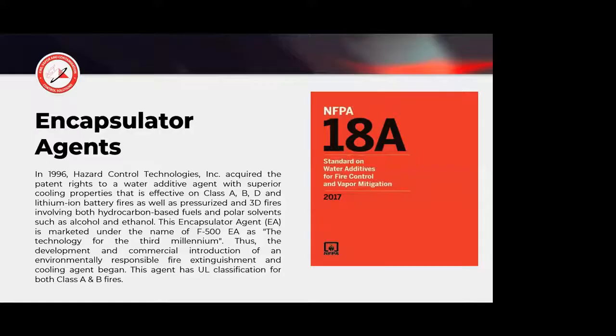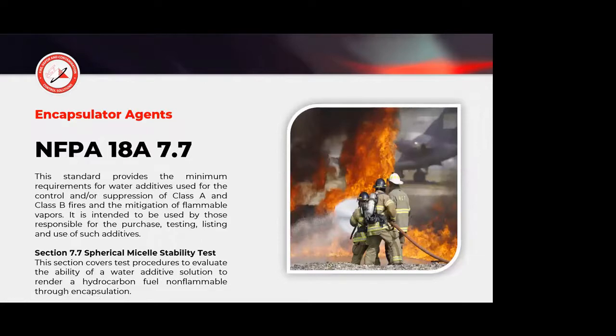So encapsulator agents. These agents are now covered under NFPA 18A. This is the standard for water additives for fire control and vapor mitigation. And it's effective on A, B, D, lithium-ion battery, as well as pressurized three-dimensional fires involving both hydrocarbons and polar solvents. More specifically, encapsulator agents are covered under, this is the qualification test. Just like you have UL 162 is a qualification test for foam. So what is that?